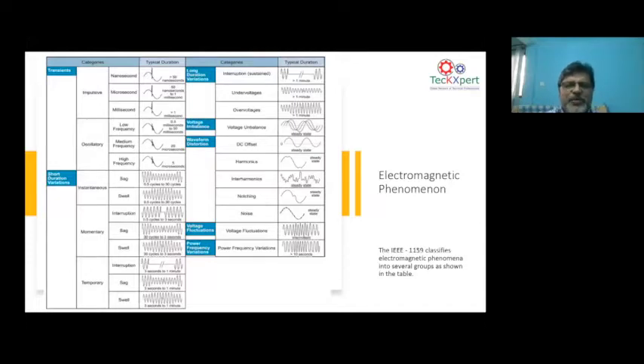So now let us look at this screen a little more in detail. On the left side, it talks about transients, the short duration variation of voltage. And on the right side, it talks about long duration variation of voltage. It talks about voltage unbalance. It talks about waveform distortions, voltage fluctuations, power frequency variations. Now, when I say conducted electromagnetic phenomena, under the IEEE 1159 they are classified in this table.